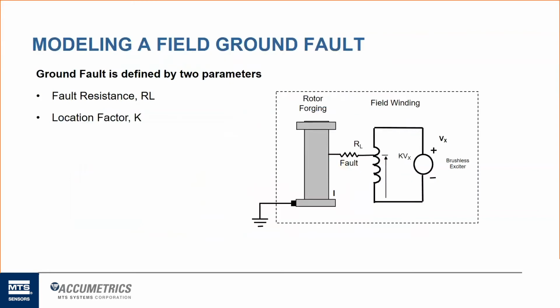So here's an example, basically modeling what a field ground fault may look like. First we have to define an analytical model for a ground fault. It's defined as some value, RL, some resistance, and some location on the field windings of the rotor. It's basically looking for the potential difference of a fault location relative to the negative side of the field windings and rotor ground itself. So 0 is at the negative side, and 1 or 100% would be at the positive side of the field windings. We provide what's called location factor, K, and we'll go into that in more detail as we cover the process of how Accumetrics measures for a ground fault.